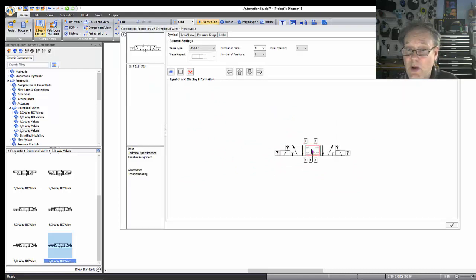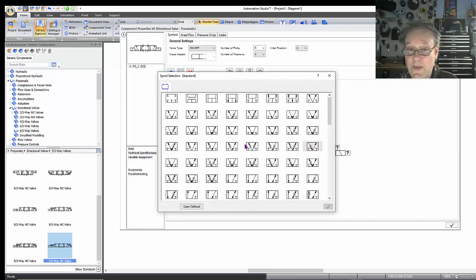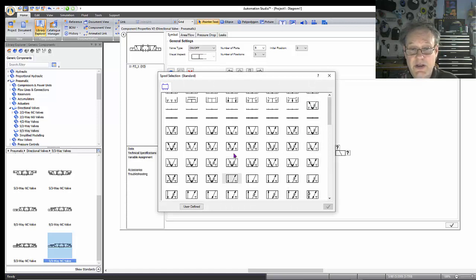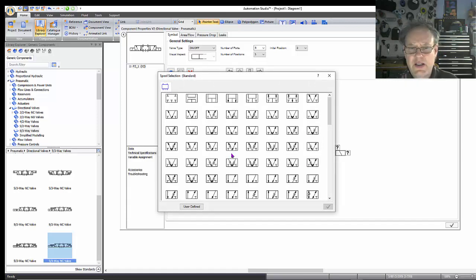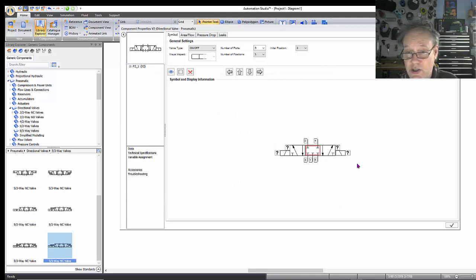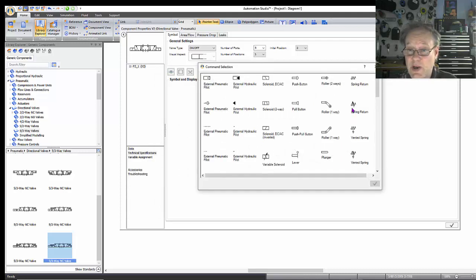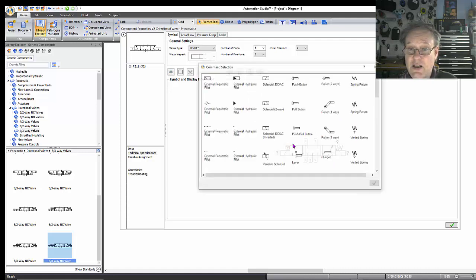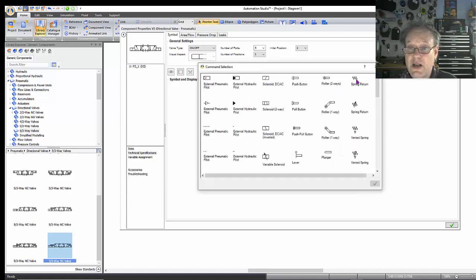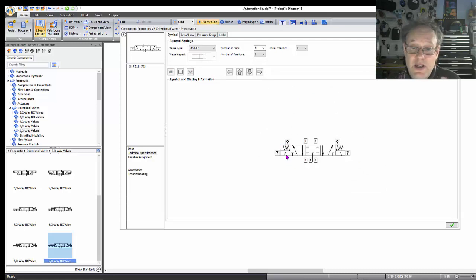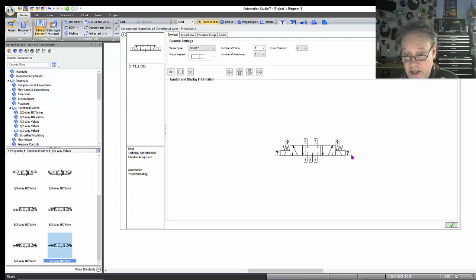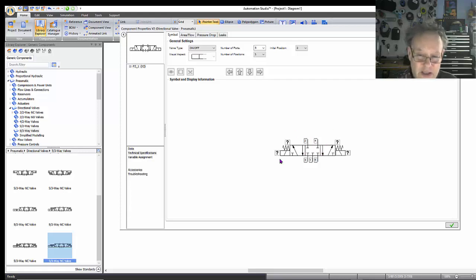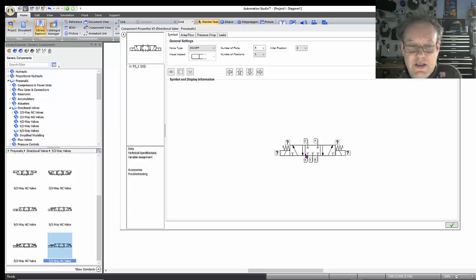Now in some cases, we may want to change this. I'm going to double click on that. And I have all different kinds of options. I can build any kind of valve I want in Automation Studio. Now in this case, I'm actually going to want to put springs on here because all of these are spring return. Actually, I've never seen one that isn't in application. Could be. But however it is, if I de-energize this and de-energize this because it's a three-position valve, I actually want it to default to the center. Just a little interesting stuff about how to build these things.